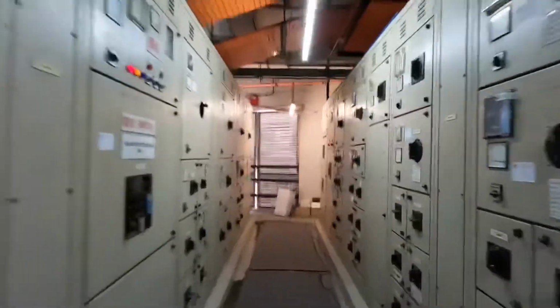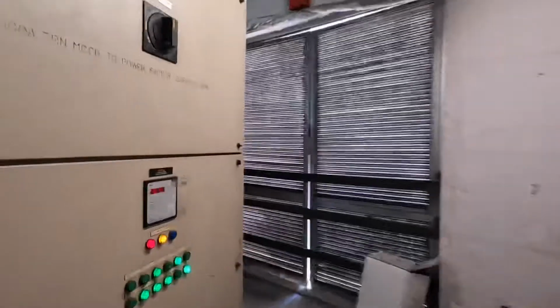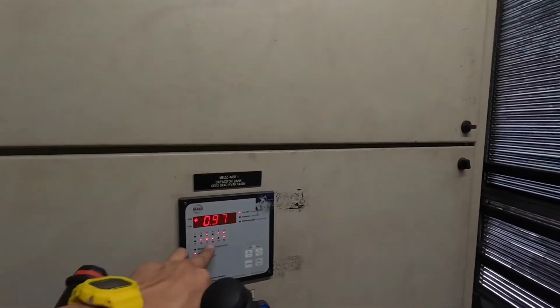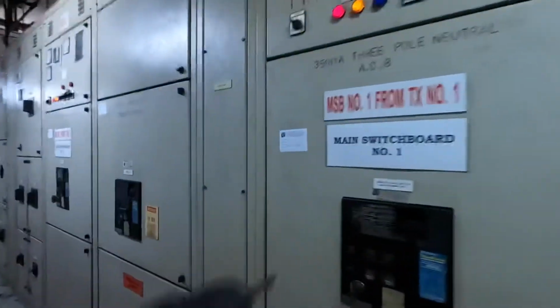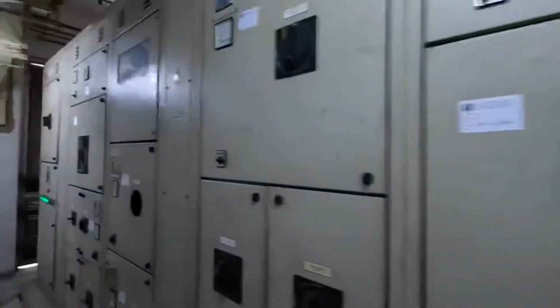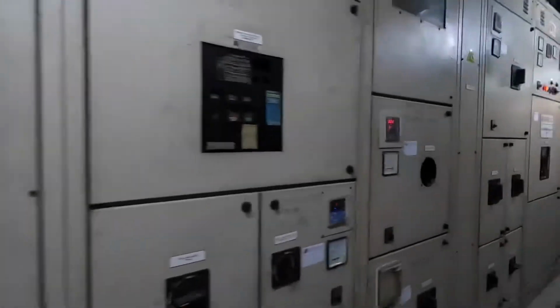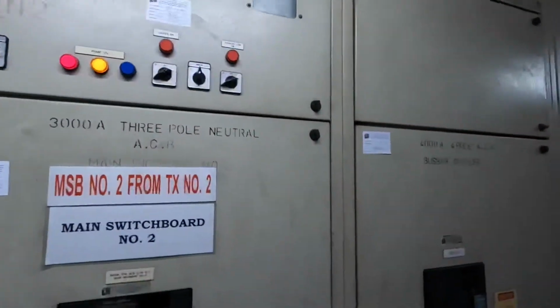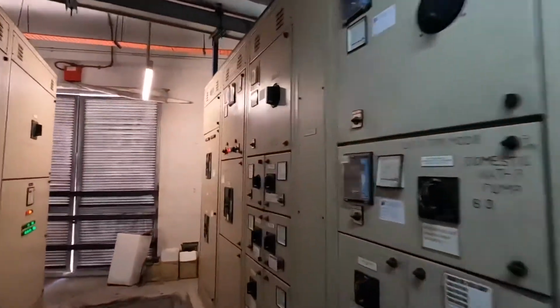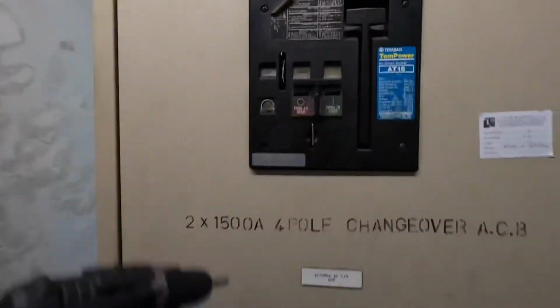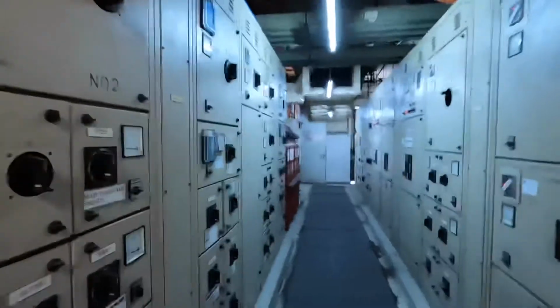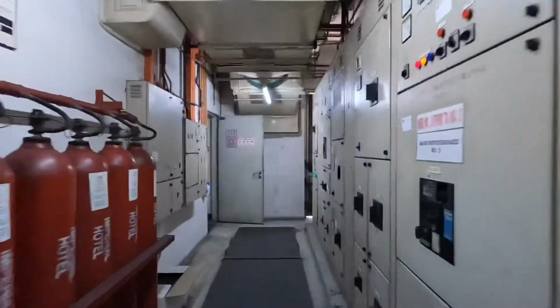Okay, here we are inside the LV room. Let's check the power factor. 0.97 inductive side. About 7 step on. MSB number 1 incomer, coupler, MSB number 2 incomer. Okay. Power factor 0.99, about 6 step on. Load is not high. We have some relay faulty. This is the changeover ACB. Okay, let's proceed to the genset room.